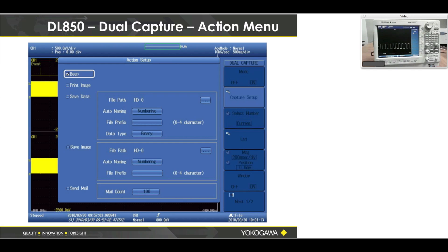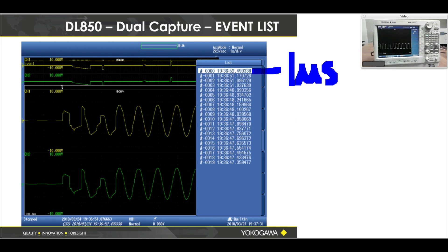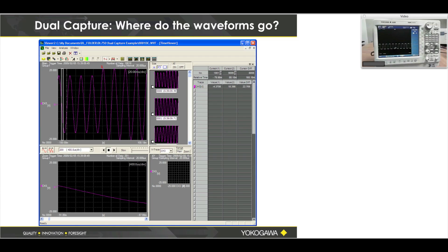Dual capture also works with actions — when I get an event I can save that waveform, which makes the DL850 more automatic. It can work in your absence; you can go home for the weekend and the DL850 will look for a surge or a sag and record those events. You also get an event list with a one-microsecond time stamp on each event, where an event would be some kind of distortion.